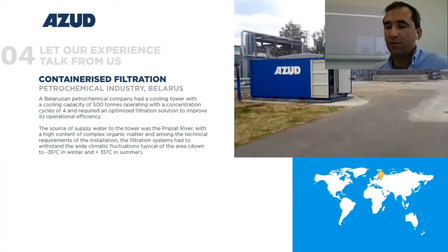Finally, I wanted to show you this case study that is also a Sidestream filtration, at a petrochemical industry. But the interesting thing about this reference is that it is a containerized solution. The environment was not the best, as in the winter we had extreme temperatures reaching down to minus 35 degrees Celsius. So the container was insulated and had a heating and ventilation system in order to maintain a constant temperature between 18 and 21 degrees for the correct operation of the filter.